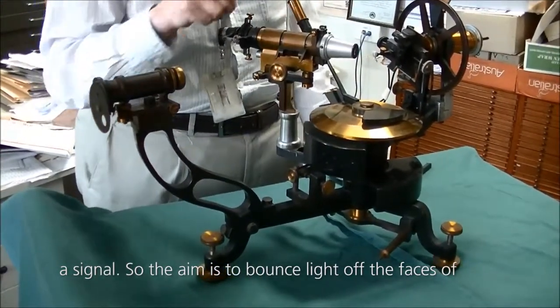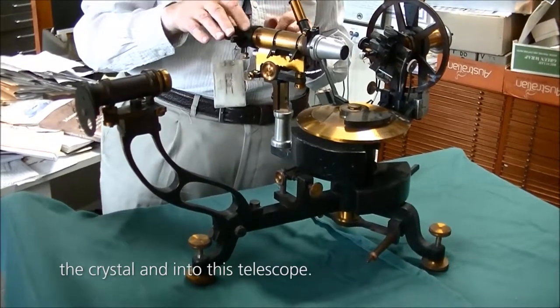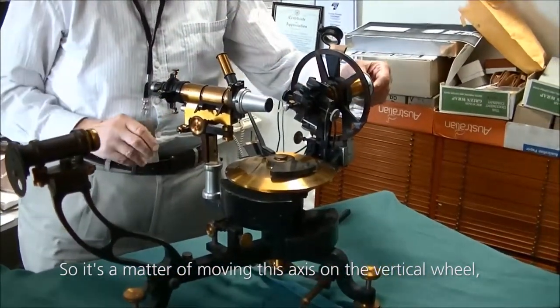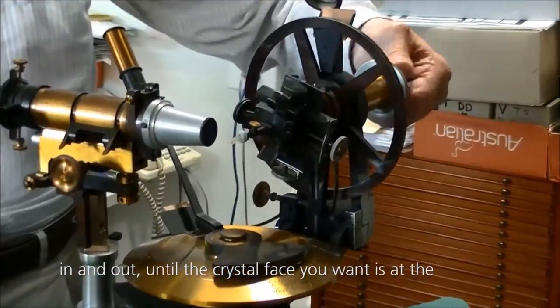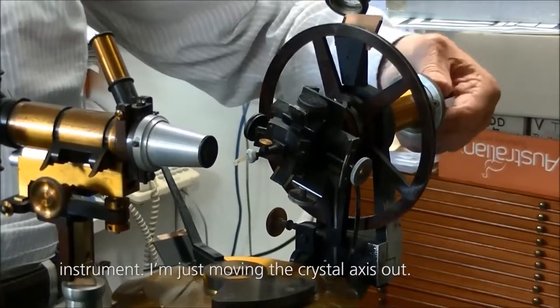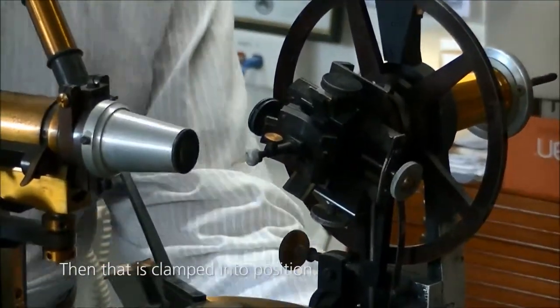The aim is to bounce light off the faces of the crystal and into this telescope. It's a matter of moving this axis on the vertical wheel in and out until the crystal face you want is at the intersection of the horizontal and vertical axis of the instrument. I'm just moving the crystal axis out, and then that is clamped into position.